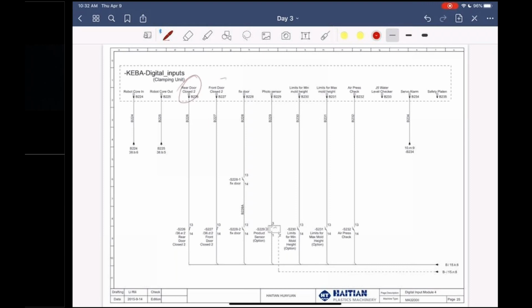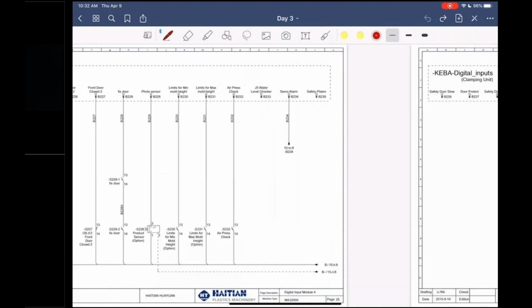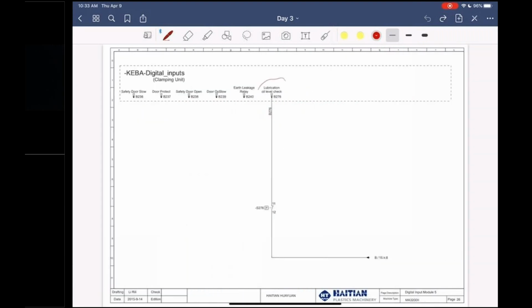You have your rear door close input, your front door close, your fixed door, which is the big door in the back of the machine. Not all machines have a fixed door. Photo sensor for your part drop. Limit for min mold height, limit for max mold height. Your air pressure check. Whenever you get an air pressure check error, it's going to say no gas. It doesn't say air, it says gas, just in case anybody ever gets that error. If you have a servo alarm, that's the input you're going to get from the servo alarm. Again, it doesn't tell you what exactly the servo alarm is. It's just going to tell you, hey, there's a problem with the servo system. Lubrication oil check is an input.